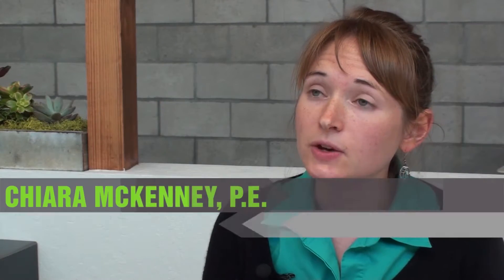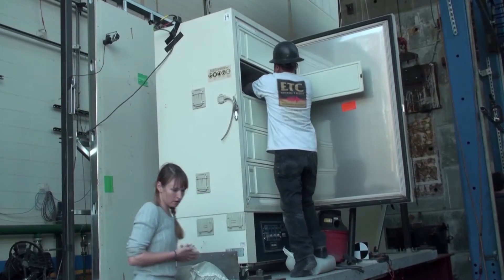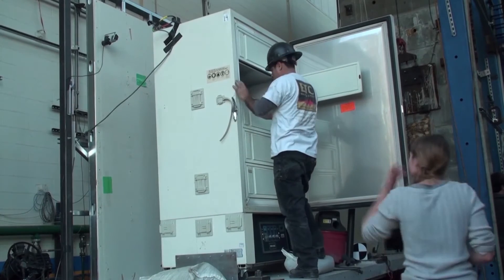For contents we used sand and lead, and we attempted to load the refrigerators with 20 pounds per cubic foot, as is specified by code.